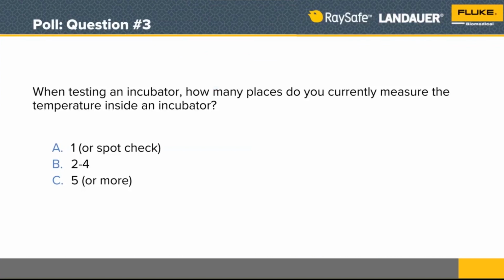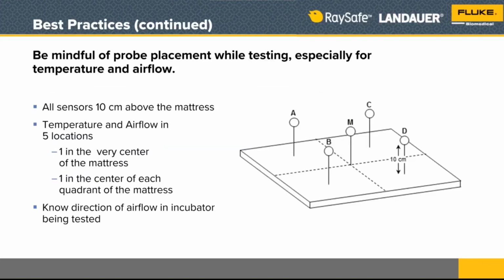Well, it's pretty split between B and C, maybe more Bs. Well, let's see what the standard says. The standard says 5. Absolutely 5 at minimum. And 1 is a central place. So think about that mattress inside the infant incubator. Imagine you divide it in 4 quadrants. You need a temperature measurement right at the center, and then you need a temperature measurement at each of the 4 quadrants in the center of those quadrants.